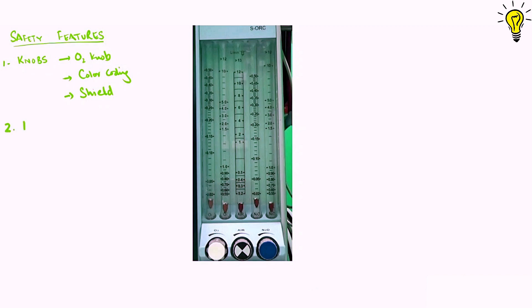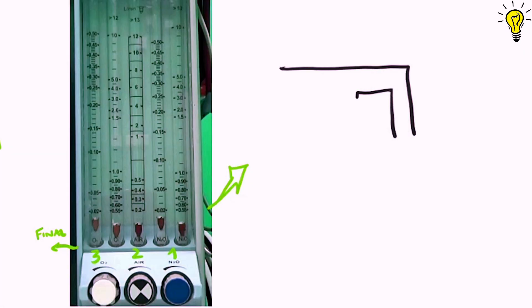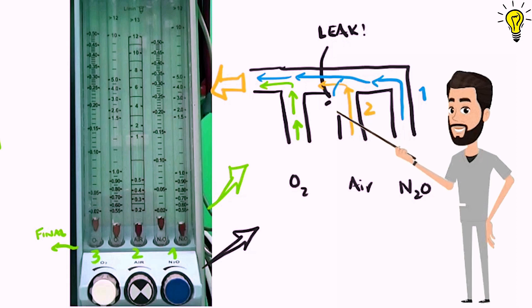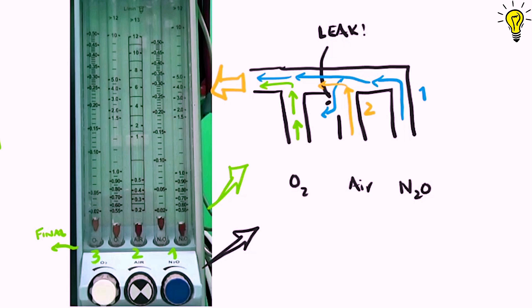Now the second safety feature is the position of oxygen downstream of other gases. Let's see. Let's draw the map of it. So you can see on the machine, nitrous oxide is at position 1, air at 2 and oxygen downstream at 3. The final mixture marked in orange big arrow at outlet. Now if there is any leak or breakage that occurs upstream of the oxygen inlet, then nitrous and air will move out of the leakage but oxygen will continue its normal path. So the final mixture will have less nitrous but oxygen content will not be affected.